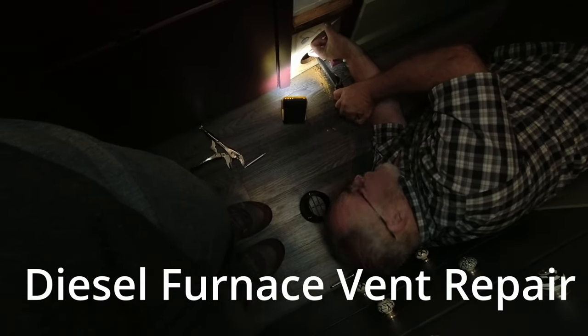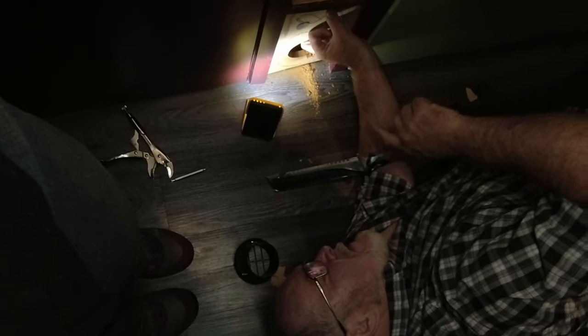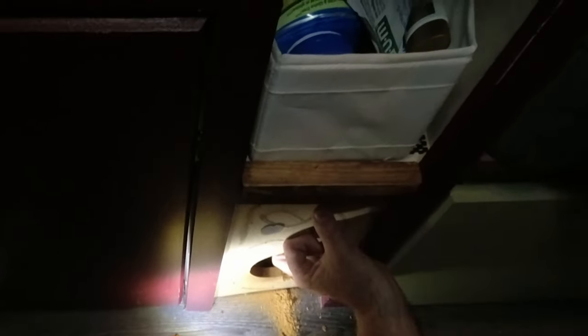So how's your night going Rob? What's happened is the furnace vent that brings the heat from the heater to the outside has come off the front duct, so now the heat is blowing underneath here and building up. I got to get this board out — I installed it from behind so I have to cut it out and hopefully break it free, then reattach this vent to the heater and pull it to the front. Then I'll put a mesh on here that I can take off.